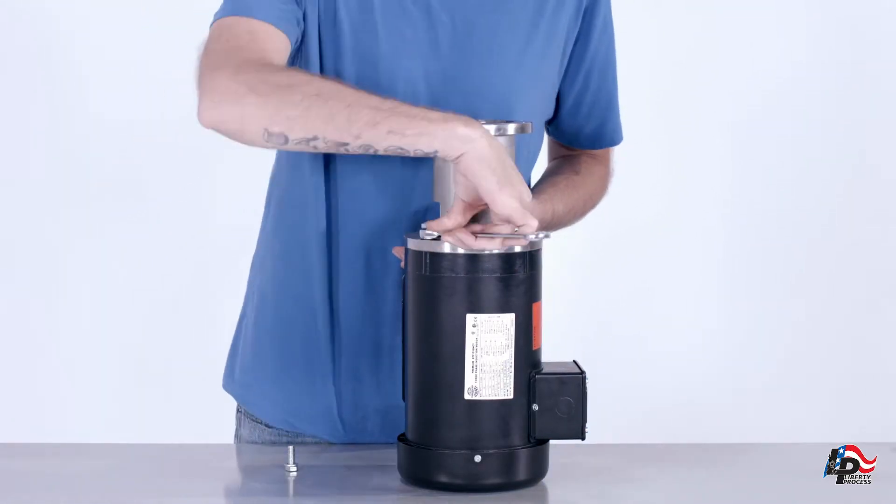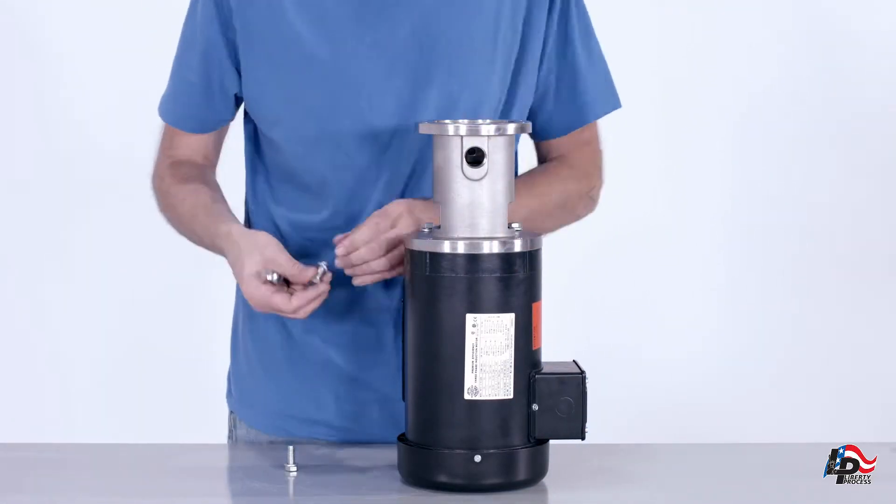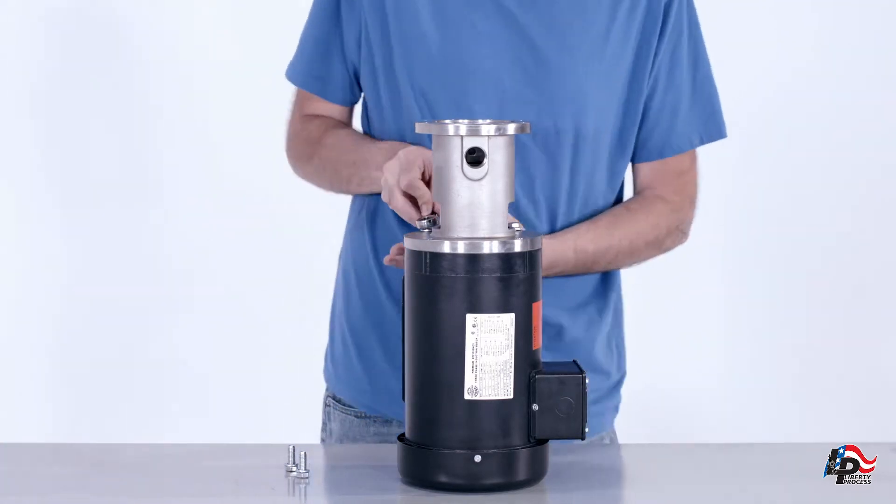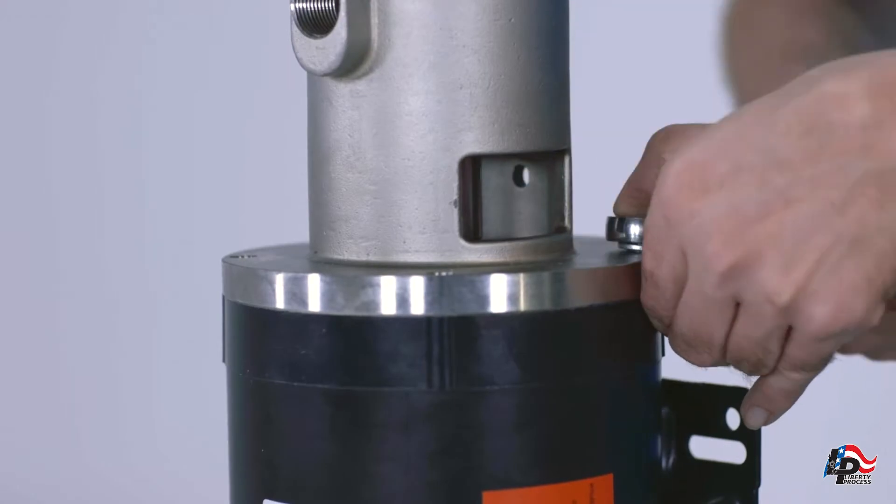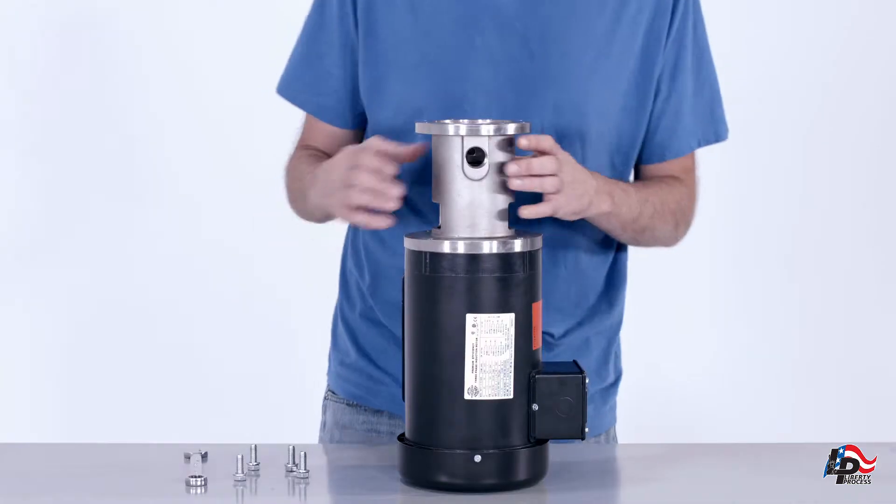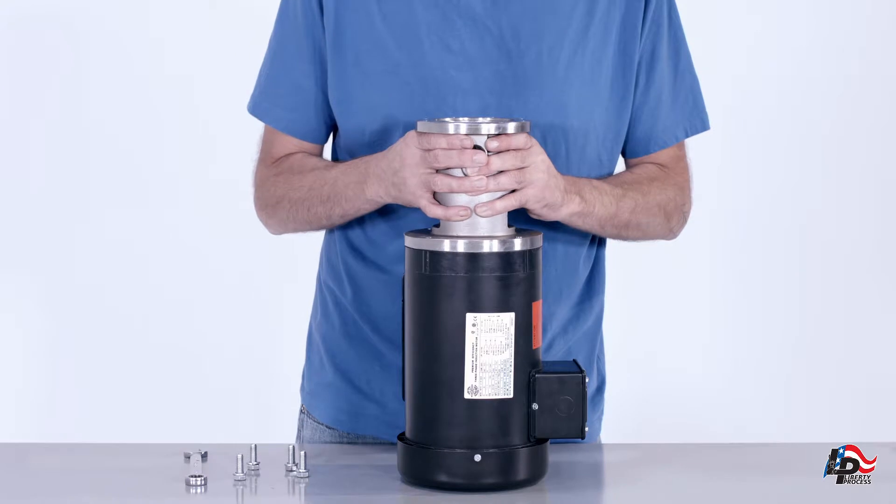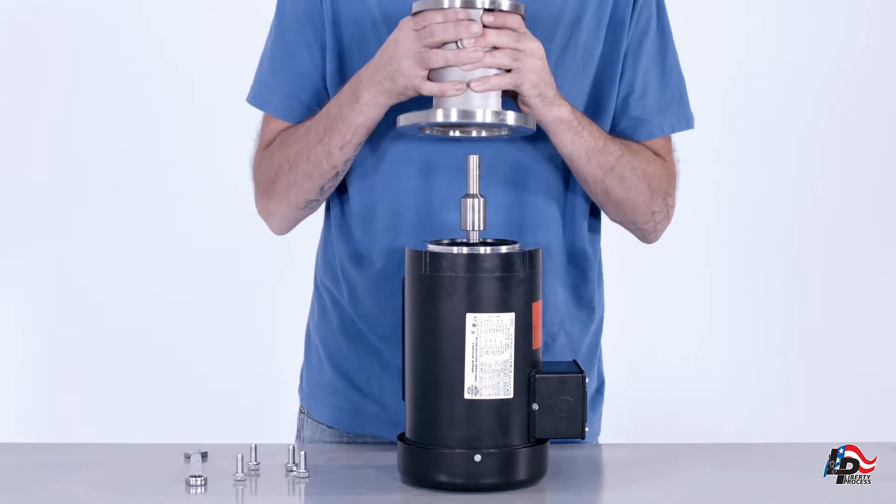The rotating face and the stationary face of the mechanical seal assembly will still be installed in the pump discharge casing. Removing the pump discharge casing from the motor will slide the rotating face of the mechanical seal assembly off the stub shaft, making the rotating face easier to remove.